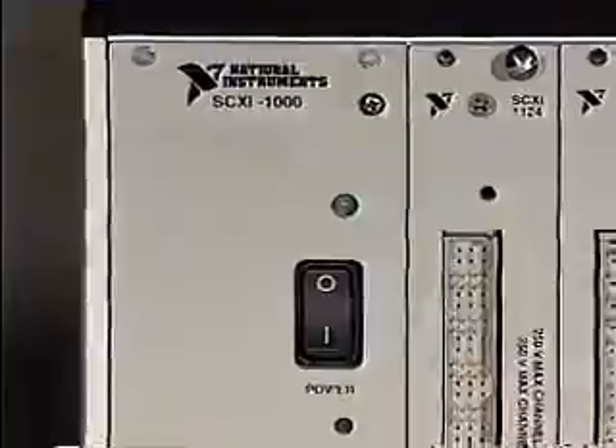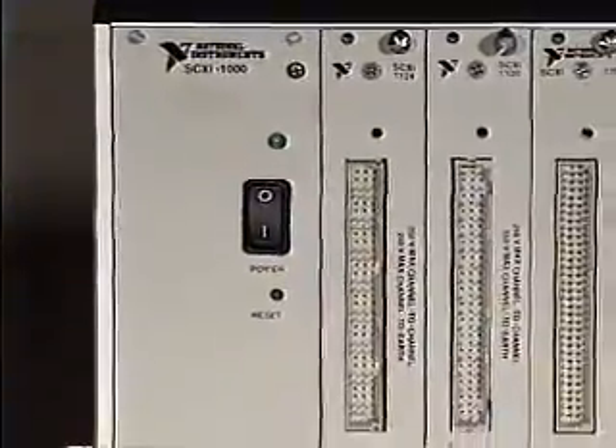An SCXI system consists of multi-channel signal conditioning and data acquisition modules installed in one or more rugged chassis. You can choose from a wide selection of analog I/O and digital I/O modules to exactly match your particular application needs. SCXI modules condition analog input signals and multiplex them onto the backplane bus of the chassis, where you can connect them to a PC plug-in DAQ board through one cable or digitize them locally with an SCXI DAQ module.